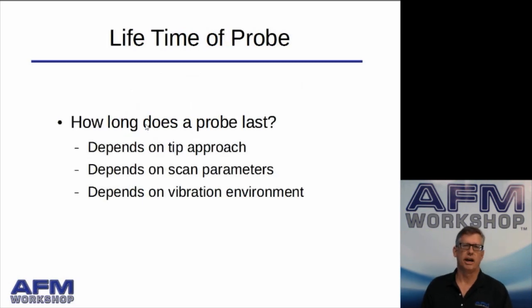One of the questions that comes up when people start to do atomic force microscopy is this first question: what's the lifetime of a probe? How long does it last? And so the answer to this question is it depends. And these are the things that it depends on right here. It depends on tip approach. So when you're running your microscope, if you're able to do a proper tip approach and the probe comes down and very gently comes to the surface, the tip will be preserved. However, if you're not careful in doing the tip approach and maybe the instrument's not tuned up, it'll hit. And if it hits, it could break the probe.